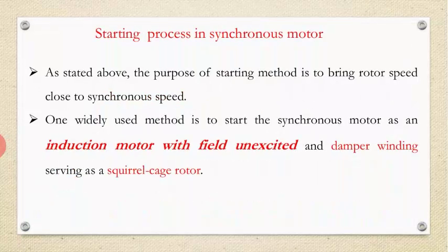Okay, so here, as stated above, the purpose of the starting method is to bring the rotor speed close to the synchronous speed. First we have to bring the speed of the rotor to the synchronous speed. One widely used method is to start the synchronous motor as an induction motor. We start as an induction motor with the field unexcited and the damper winding serving as a squirrel cage rotor. I have already discussed this point.